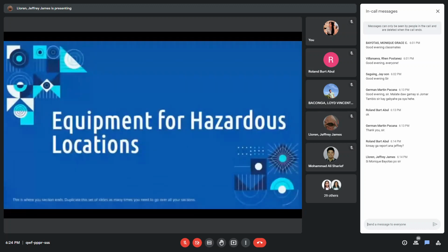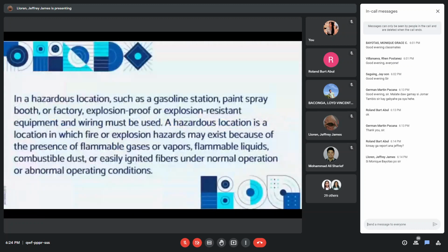So the second subtopic is equipment for hazardous location. In hazardous locations such as gasoline station, paint spray booth, or factory, explosion-proof or resistant equipment and wiring must be used. A hazardous location is a location in which fire or explosion hazard may exist because of the presence of flammable gases or vapors, flammable liquids, combustible dust, or easily ignited fibers under normal operation or abnormal operating conditions.